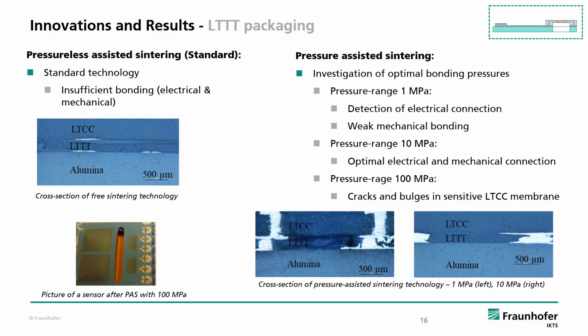In the pressure range of 1 MPa, an electrical connection is there, but as you can see in the cross-section, the mechanical joint is weak. In the pressure range of 10 MPa, we found the optimal parameters. We have a good electrical and mechanical connection. You can see it on the right. But if the pressure is too high, cracks and bulges occur in the sensitive membrane, which is shown in the picture down left. So we could establish a functional joining technology which combines electrical and mechanical joint in one step and for high temperatures.